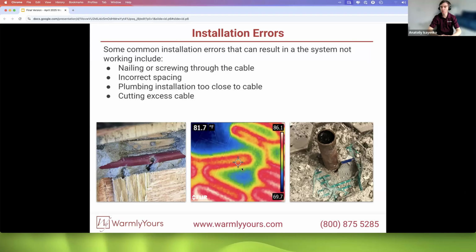But yeah, there was some plumbing work. Again, we can speculate. There was some plumbing work done after the fact, and that heating system layout or information or general knowledge was not shared to the person doing that work, and that pipe went right through the cables. So again, another example of incorrect installation, but also the potential troubleshootings that can be done later on to get that resolved.